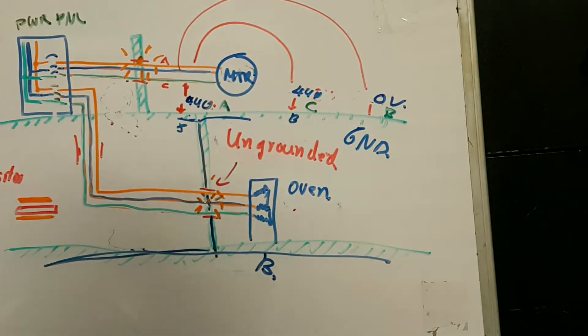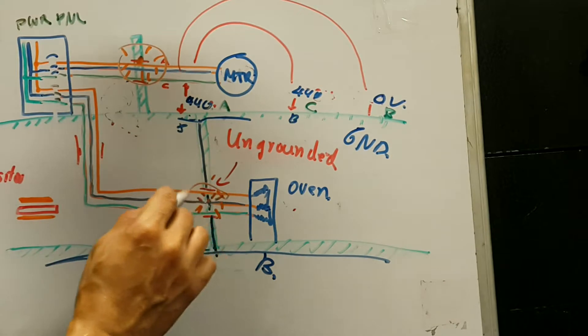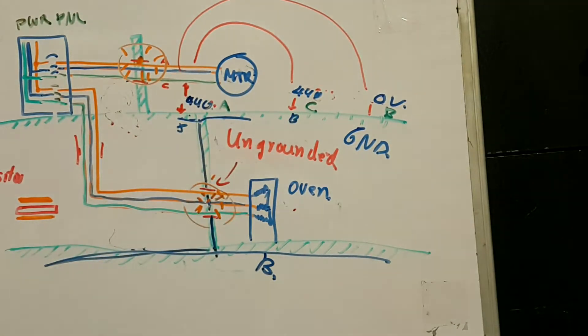That's why, whenever we get grounds on board the distribution system, we got to clear them as fast as we can, before another ground shows up, to prevent these massive class C fires and equipment getting damaged.